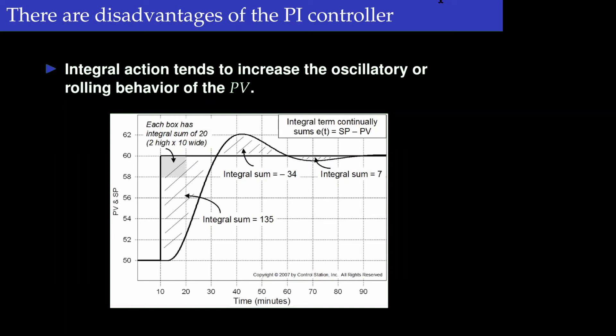In doing this, although the output is approaching steady value, the integral action keeps on increasing because it is summing all the errors — the area under the curve keeps growing even as the output approaches the set point. Consider a tank level controller: the level is approaching the set point, but the control action keeps increasing due to the integral of the error, so the level will go beyond the set point value.